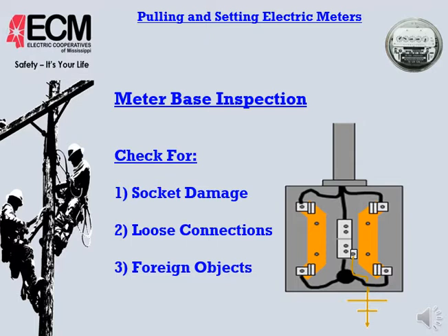We're looking for loose connections. Of course, if you don't find the loose connection, and you feel you have one, eventually it will show you where it's located. Loose connections generate a lot of heat. And the problem with that is when you have a loose connection, it generates heat, and that heat makes the loose connection worse.